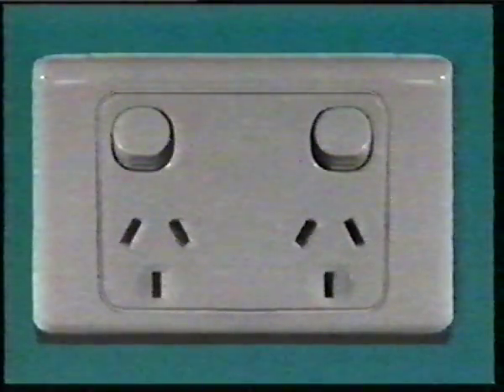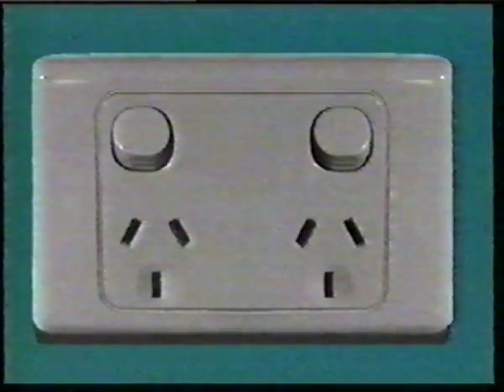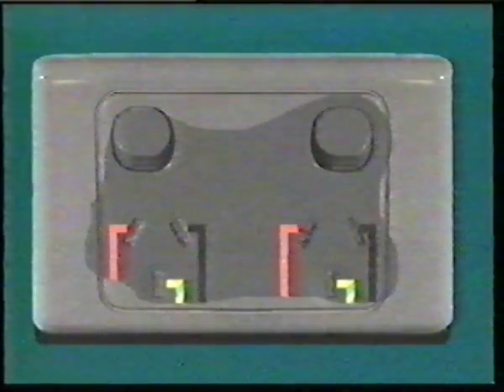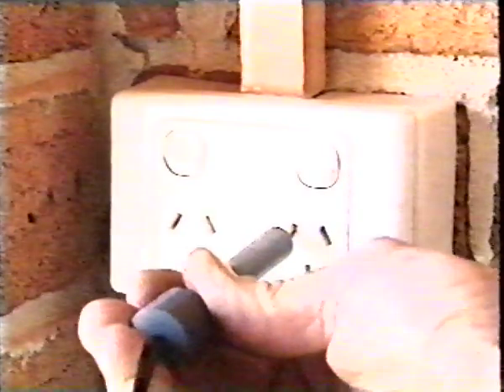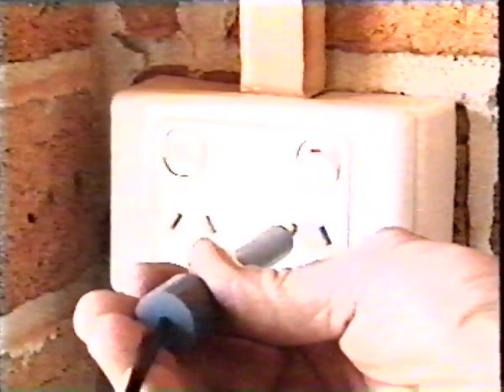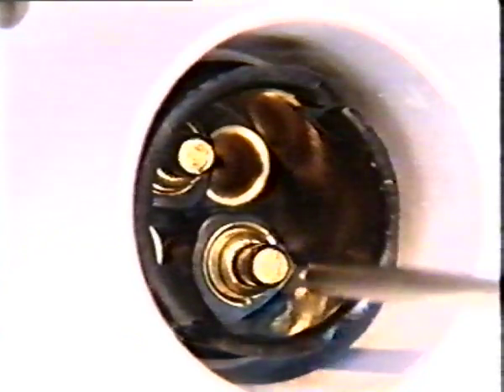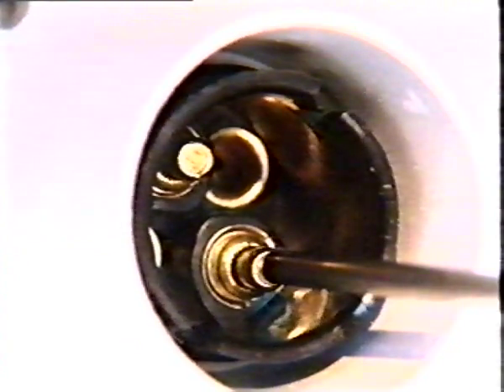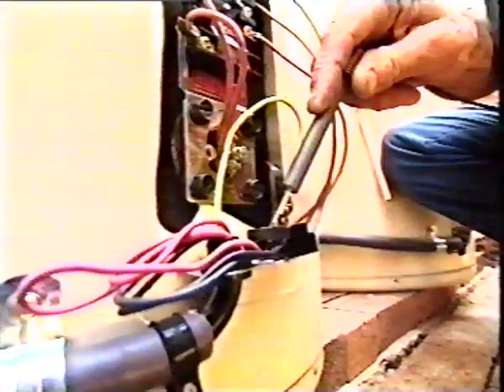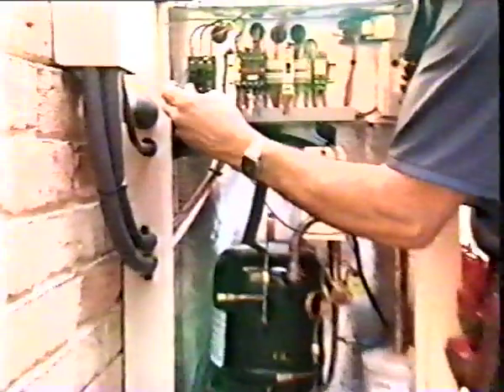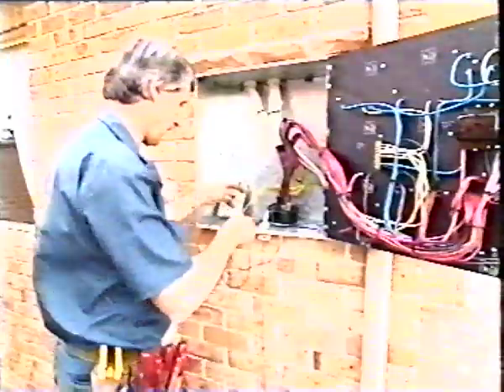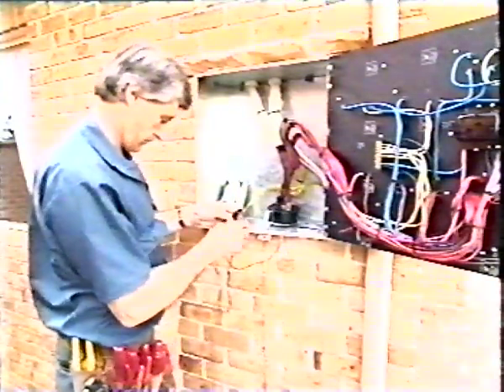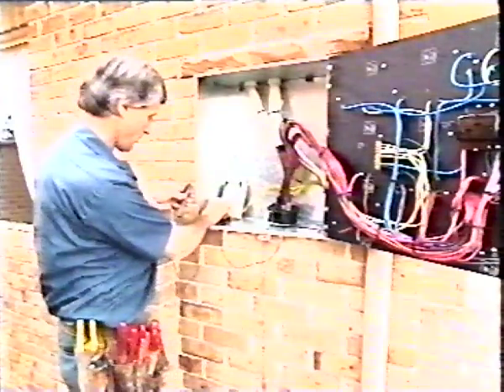In the case of general purpose outlets and other socket outlets which accommodate flat pin plugs, they should be connected so that when viewed from the front of the socket outlet, earth, active and neutral are connected in a clockwise order. For this test, we need the ohm meter and a 60-watt lamp. The test is generally performed on the contacts of socket outlets, contacts of lamp holders or the terminals of their associated switches. It depends on the methods used. Terminals provided to connect equipment such as water heaters, ranges and air conditioners to the fixed wiring. The following demonstrations show how correct polarity can be established when the supply is not available.